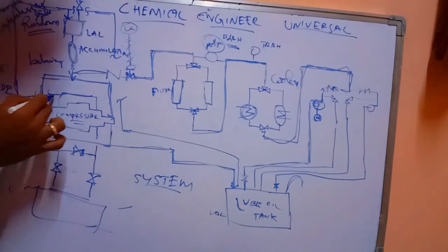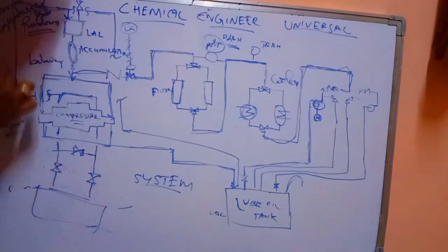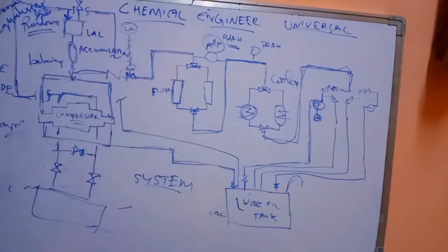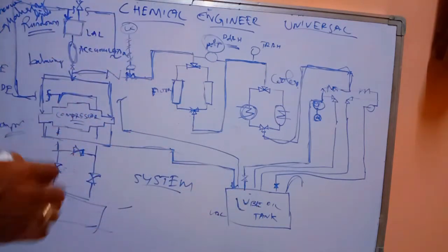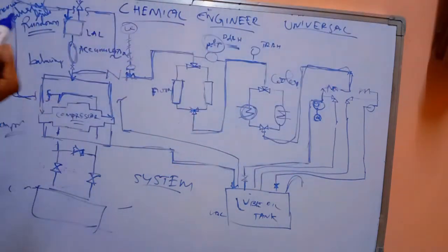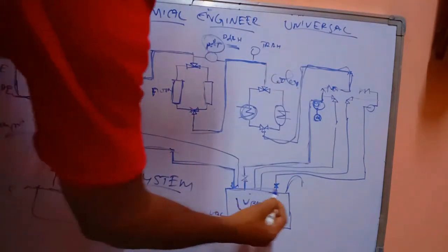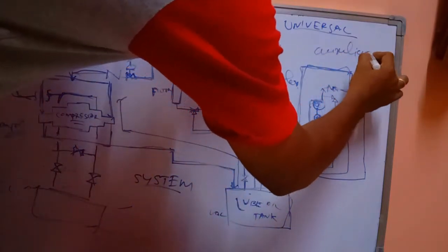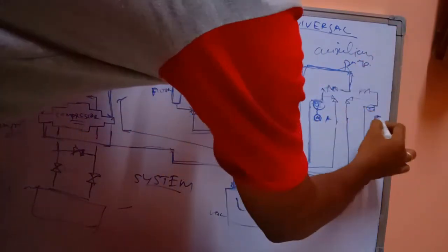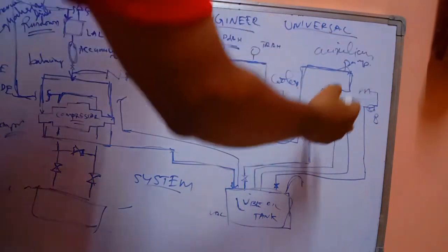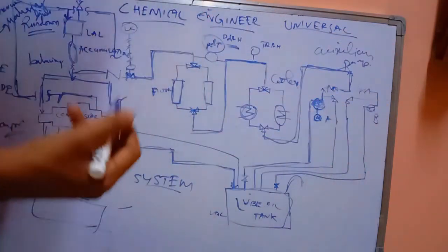So this is the line. The line is taken from the balancing lines, and it will connect to the rundown tank and as well to the main lube oil tank. So during the startup, now we will see the startup again. We have a tank. So the auxiliary pump started. We have two pumps here, pump A and B. So if one pump fails, the second pump will start. That will be decided based on, those will be controlled by the DCS system.